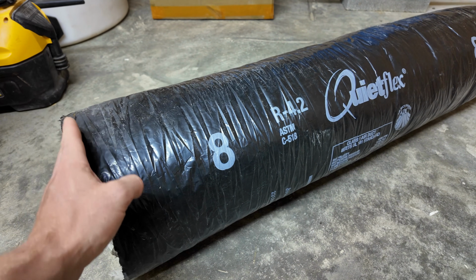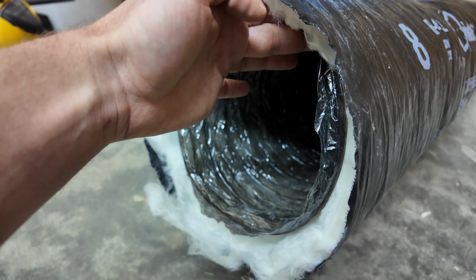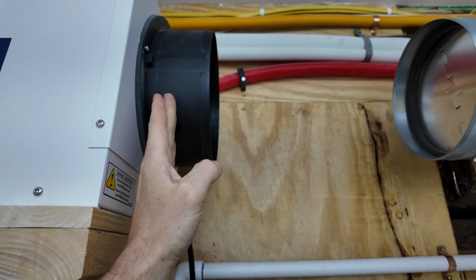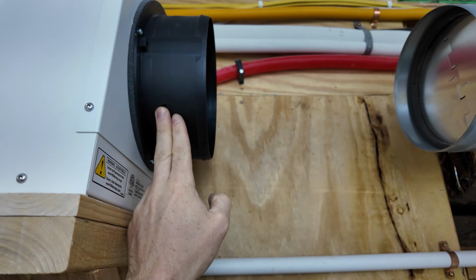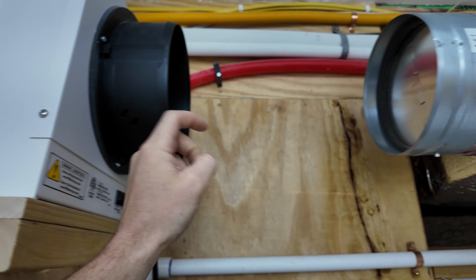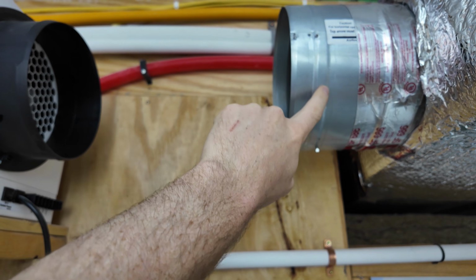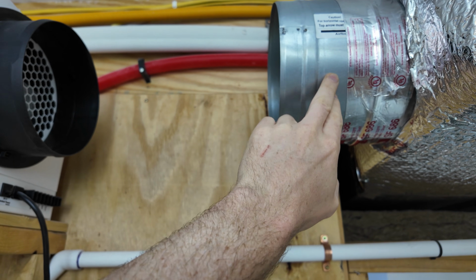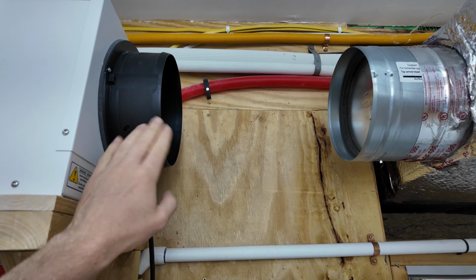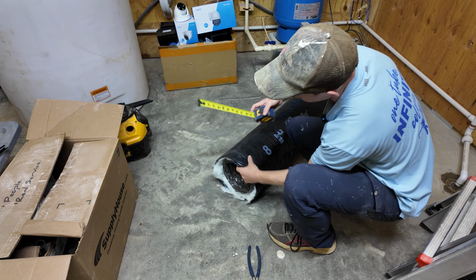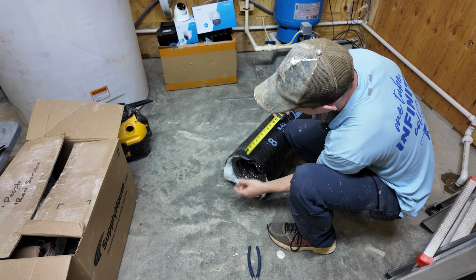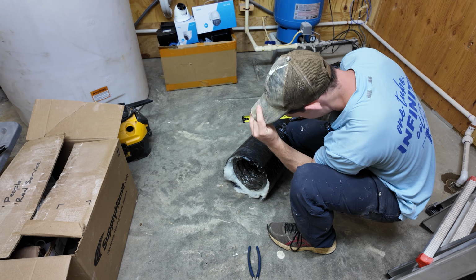I'm going to cut the insulation a little bit longer than the actual tube itself. The inner lining needs to stop a little bit short so I can still wrap it with tape to seal it, and there are little ledges, or beads, that the inner lining has to go over top. But I need a little bit of extra fiberglass to go all the way up to the unit. So I'm going to keep the insulation at 22 long and the jacketing at 18.